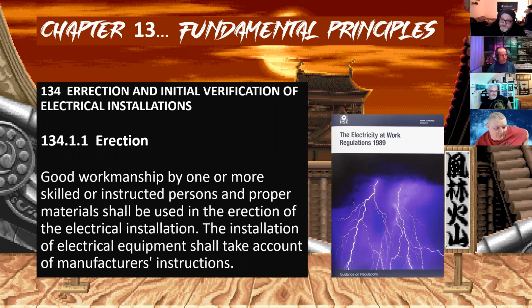134.1.1 erection. Good workmanship by one or more skilled or instructed persons and proper materials shall be used in the erection of the electrical installation. The installation of electrical equipment shall take into account manufacturer's instructions.